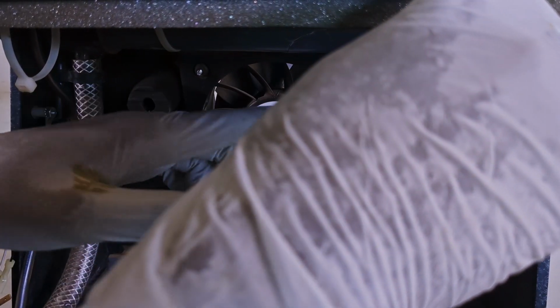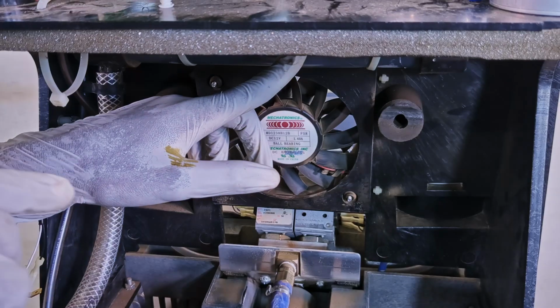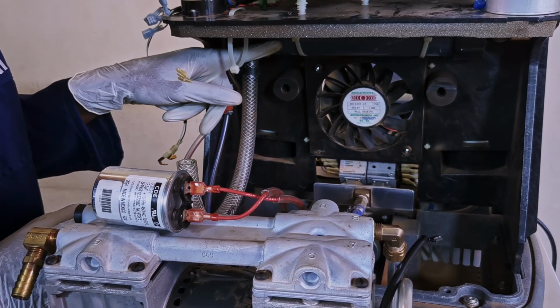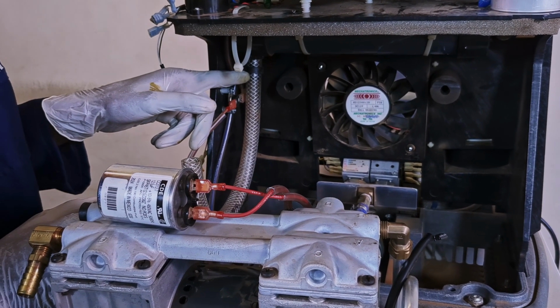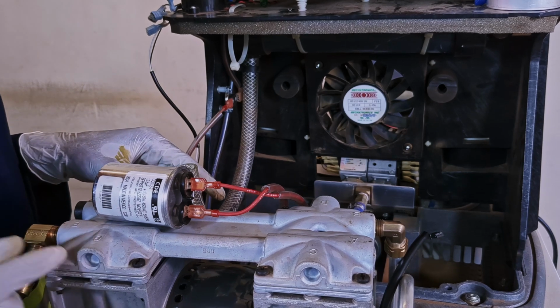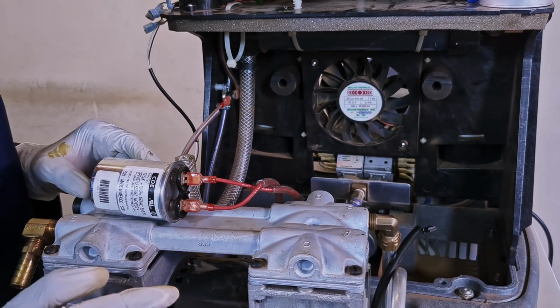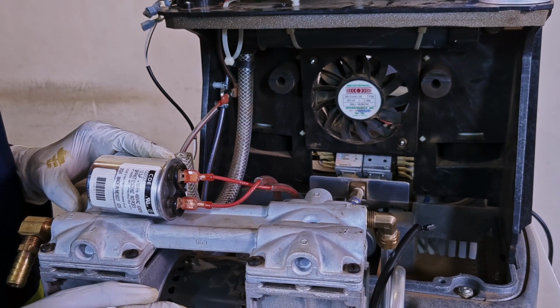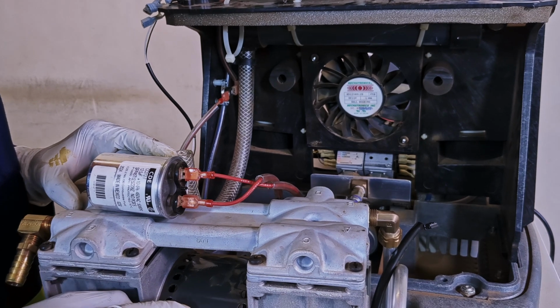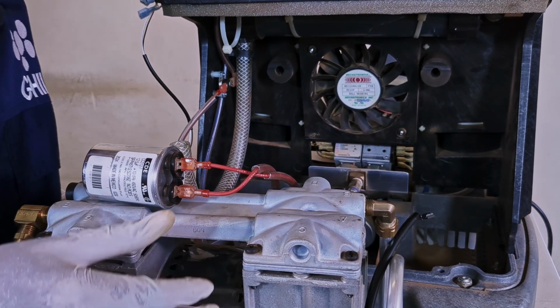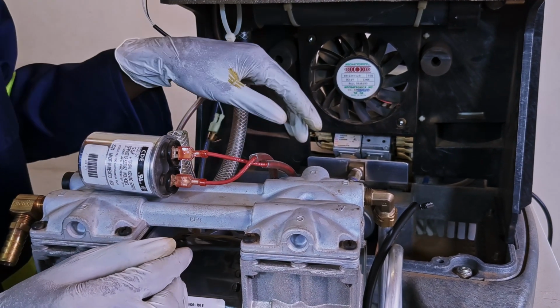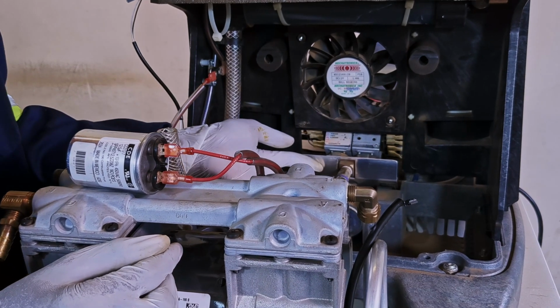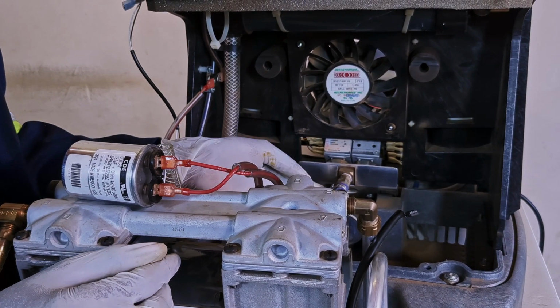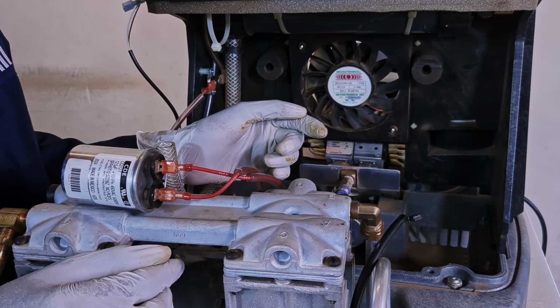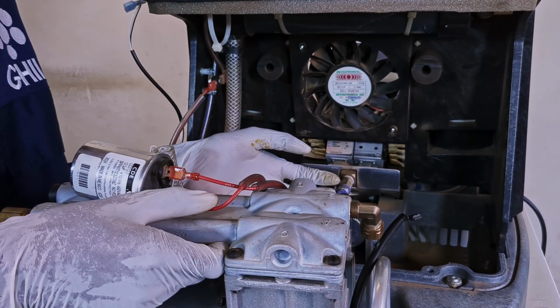From the fine particle intake filter, air then passes to the intake muffler. From the intake muffler, air passes through the intake hose to the compressor. The compressor then raises the air pressure up to 40 psi. This compressor is connected to the 4 solenoid valves, which consist of 2 feed valves and 2 waste valves.